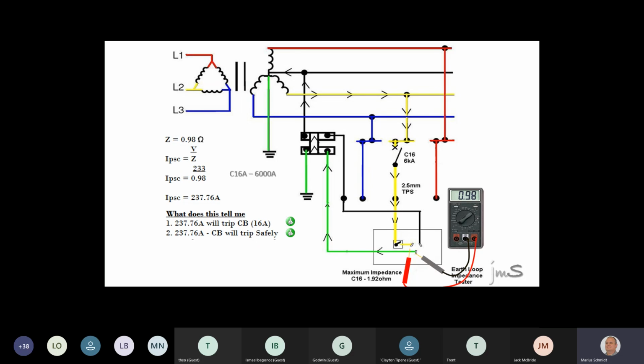So the question is, if this was 7,000 amps, that breaker is going to blow up if there was a dead short. So you must always make sure that your short circuit current is within the limits. If not, you have to go buy one with a bigger kA rating. All right? Great. And here comes the third question.